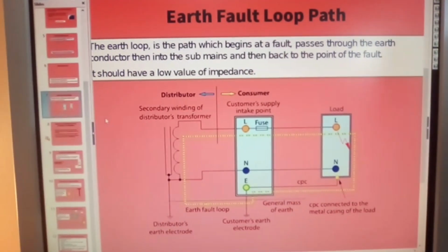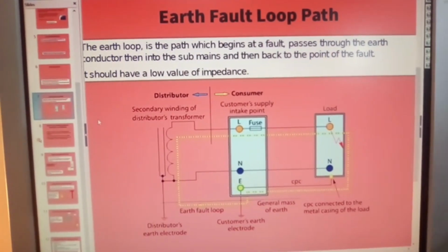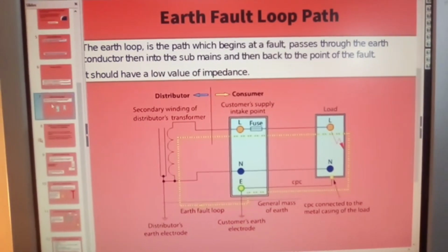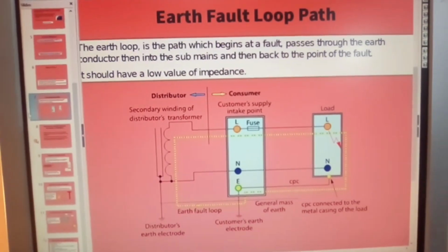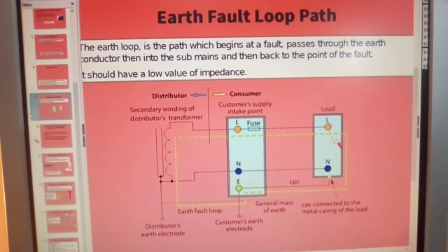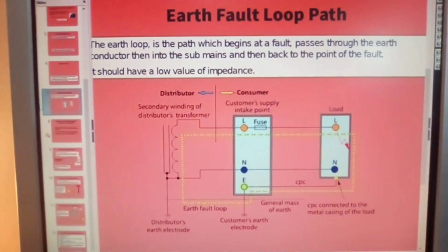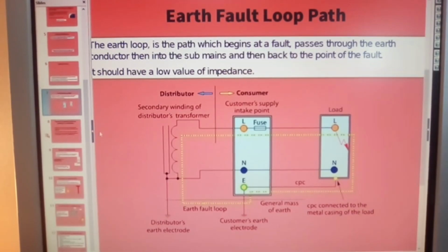There were 5 circuits on this fuse board. I mean, there's 12 altogether, but this particular RCD controls 5, and of those 5 circuits, none of the circuit breakers tripped out, but the RCD did trip out. But I suppose you can say it's actually done its job, which I would agree with. The main thing was it was quite safe.